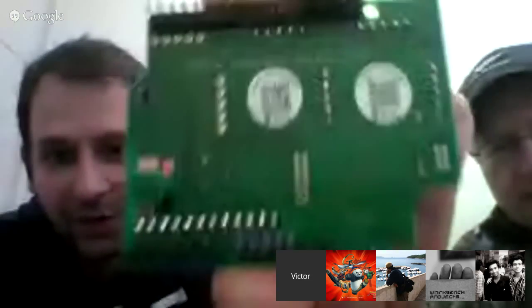Now, the gas sensors themselves are completely analog devices, so there's no intelligence on the sensors in this case. What the manufacturer gives us is a QR code connected to each sensor. Every shield, you can see, we stick the manufacturer's QR codes on the back as a kind of historic record of what sensors are on which product. In software, we put in those parameters so the circuitry can be configured for the sensors, and the interpretation of the response is tailored to those parameters.